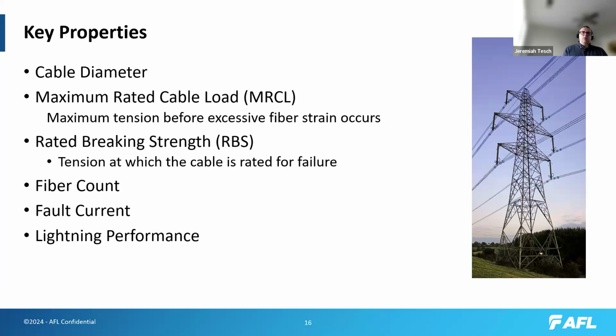The maximum rated cable load, in contrast, is for the fiber. This is typically from 60 to 80% of the rated breaking strength, and this is the maximum tension you should actually design for before the fiber will experience excessive strain and permanent damage. So if you're looking at OPGW, you need to take note of both the MRCL and the RBS in terms of tension ratings. And then you also, of course, have your cable diameter, your fiber count, fault current, which is its capability to run excess current to ground, and then the lightning performance. So these are some of the key properties of OPGW.